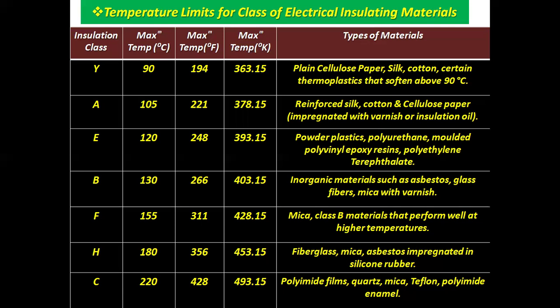F: 155 degrees centigrade maximum temperature withstanding ability, 311 degrees Fahrenheit, 428.15 degrees Kelvin. Mica and class B materials that perform well at higher temperatures. H: maximum temperature withstanding ability 180 degrees centigrade, 356 degrees Fahrenheit, 453.15 Kelvin. That is fiberglass, mica, asbestos impregnated with silicone rubber. C: 220 degrees centigrade, 428 degrees Fahrenheit and 493.15 degrees Kelvin maximum temperature withstanding ability. Polyimide films, quartz, mica, Teflon, polyimide enamel.